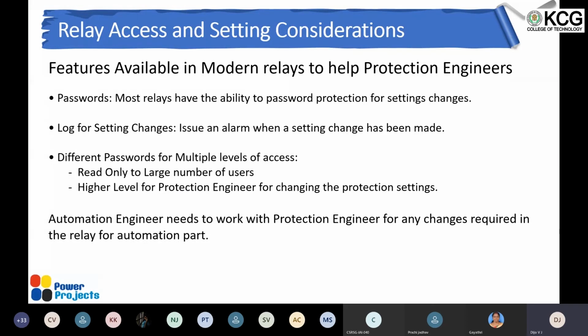Maybe some people at automation level use that network for some other purpose, but by mistake, or maybe somebody wanted to intentionally do it, they can change the setting of the relay also from the communication network. So what the relay gives as an option to the protection engineers is that passwords can be set in the relay, so that if somebody wanted to change some setting, they need to enter a specific password. There are different levels of password available in the relay. One is for viewing. Viewing passwords may be given to many people, but the password for changing settings will be handled by maybe one protection engineer who is the custodian of that particular area.